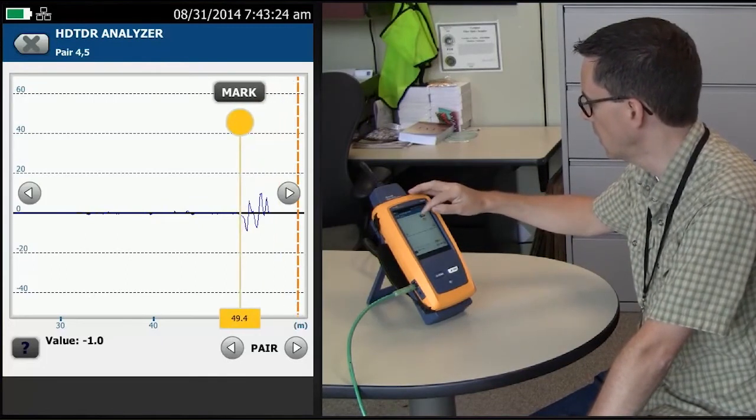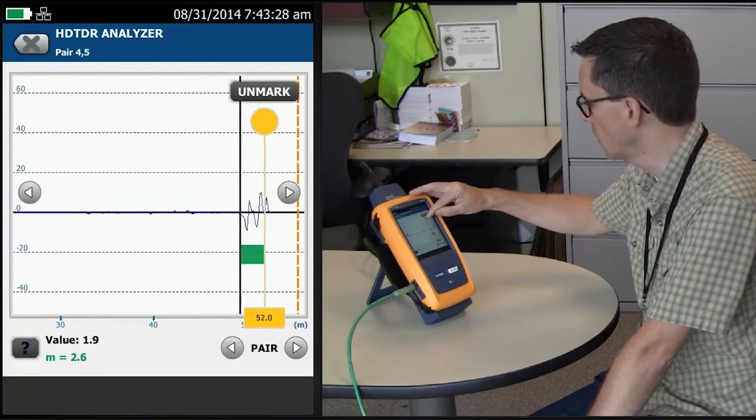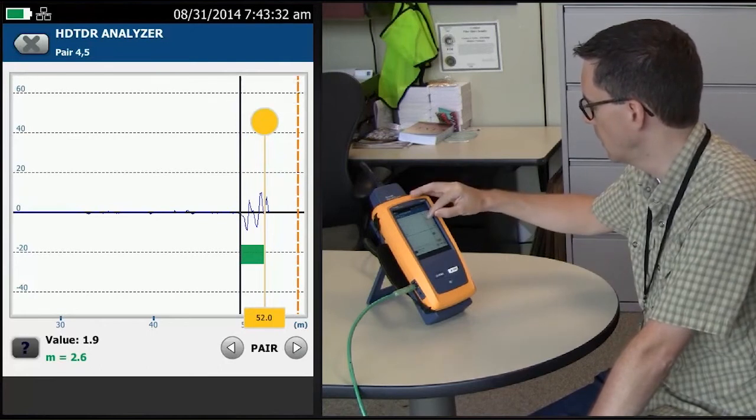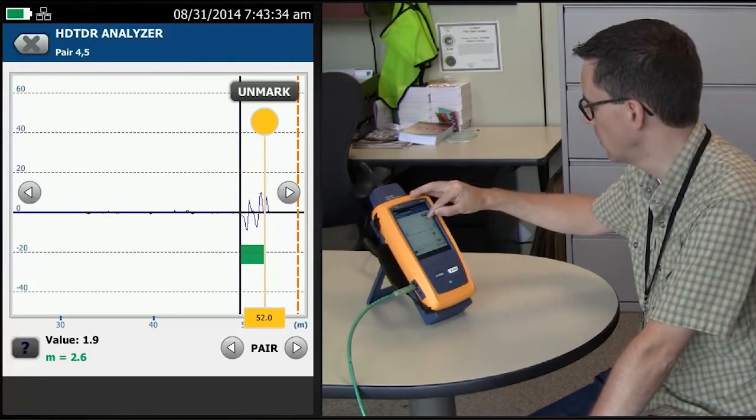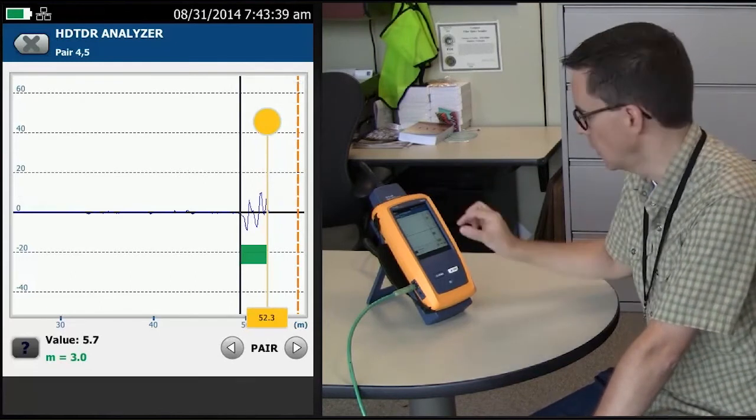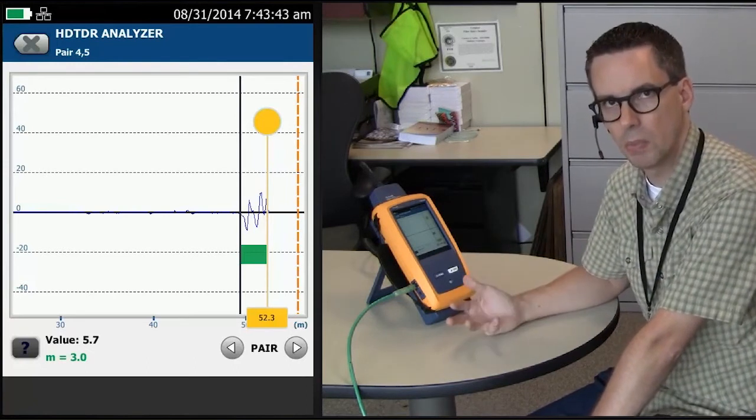If I mark it and bring it across like this, I say to about there, maybe a little bit more than that, I was probably there. What this is telling me is, with this significant impedance anomaly going on here, is in the last three meters.